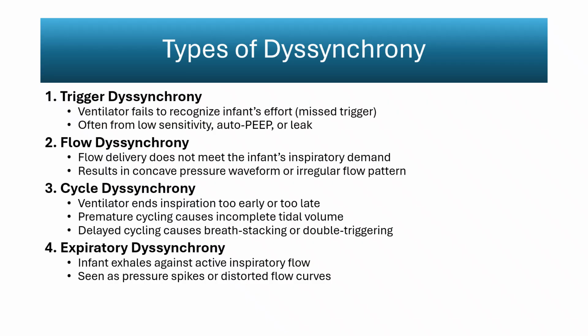Cycle dyssynchrony occurs when the ventilator terminates inspiration at a time that does not match the infant's neural timing. If inspiration ends too early, premature cycling, the infant receives an incomplete tidal volume and may immediately attempt to re-inhale. If inspiration ends too late, delayed cycling, the infant is forced to exhale against ongoing inspiratory flow. This can produce breath stacking or double triggering, where two ventilator breaths occur for a single infant effort.